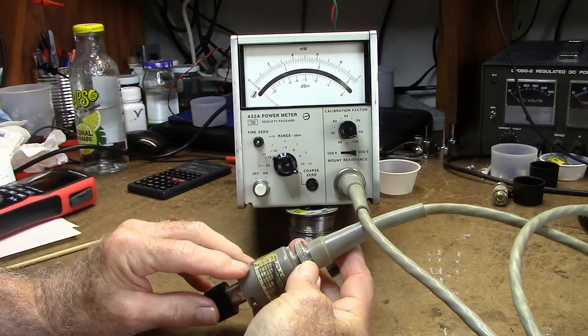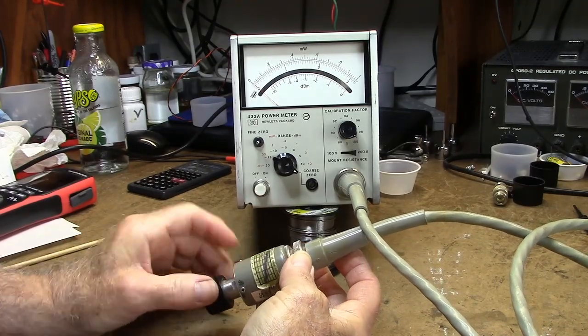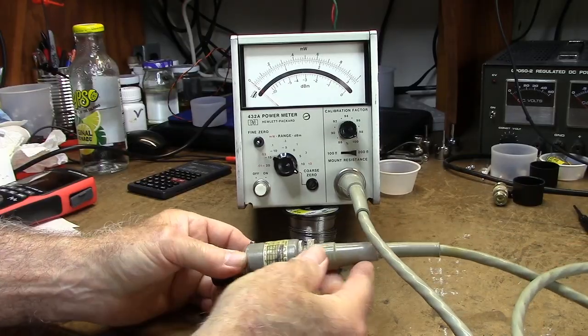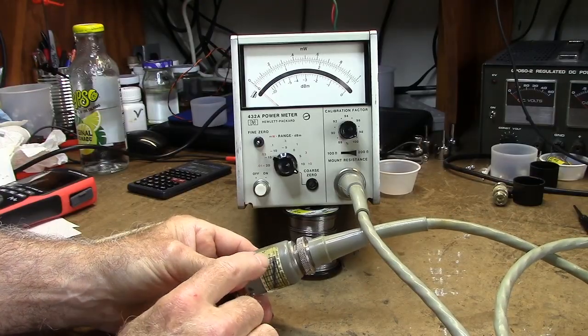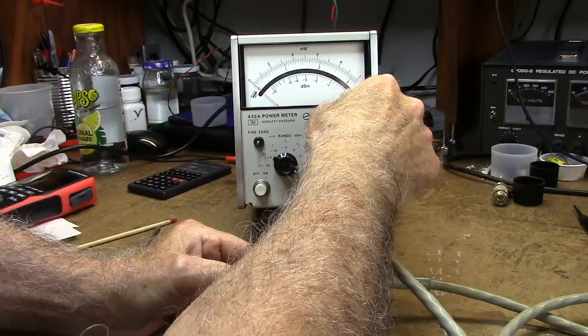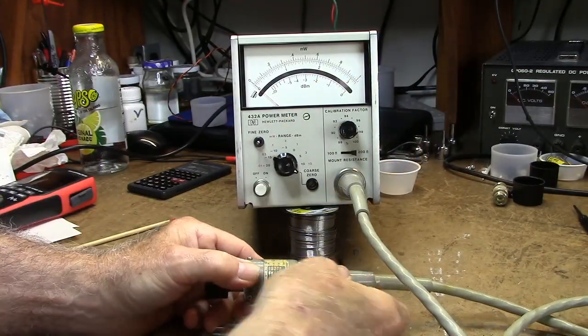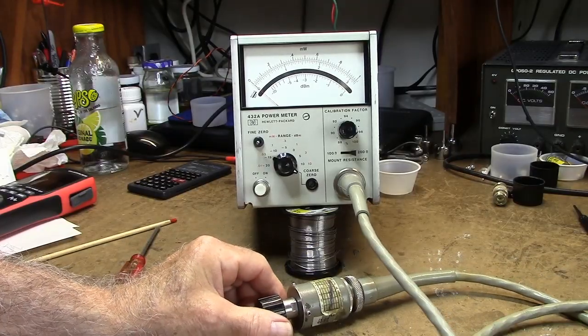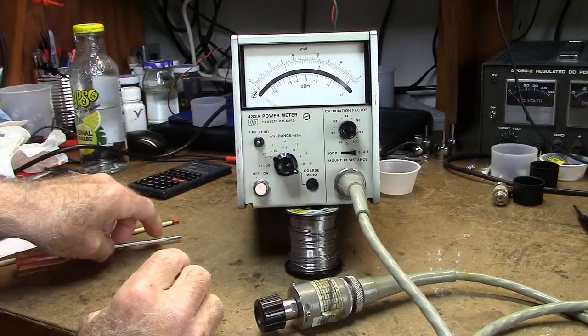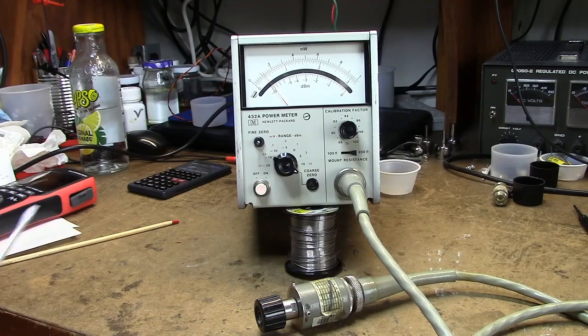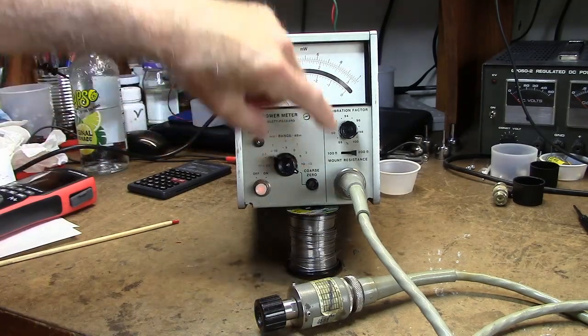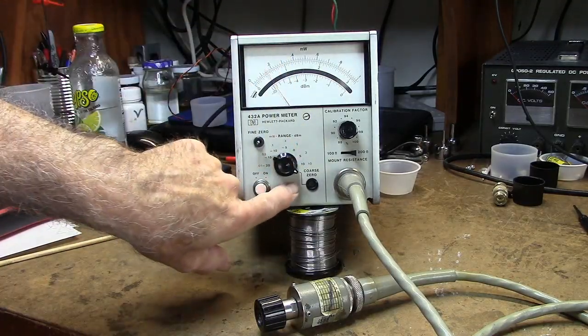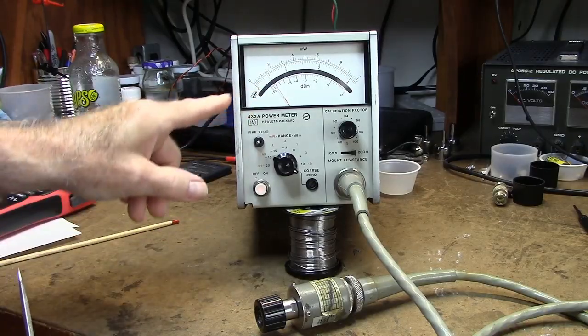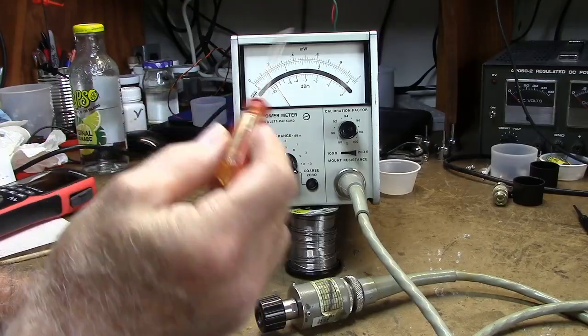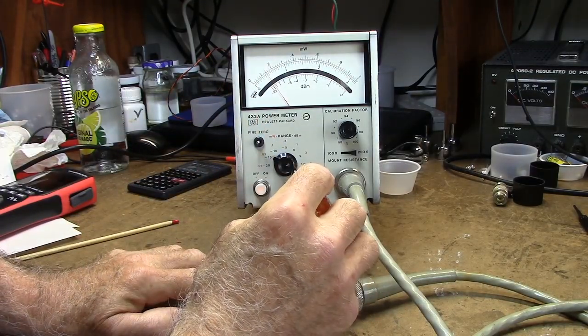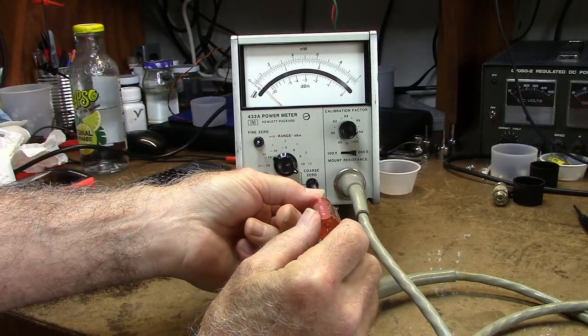There's a chart, and it goes from basically 10 megahertz to 18 gigahertz, and it shows that as you go up in frequency, the calibration factor decreases. So up near the top here, I'm going to set it up for the high end here, probably 98 or whatever. When I pick a frequency to put in this thing, I'll readjust the calibration factor. Anyway, I'm going to turn the power on now. And according to the instruction manual, what you do is you put the selector range switch here on coarse 0, and then you want to set the needle to 0. Of course, you do the mechanical adjustment first. I did that earlier. So then you should be able to set this to 0 with the coarse 0 pot.